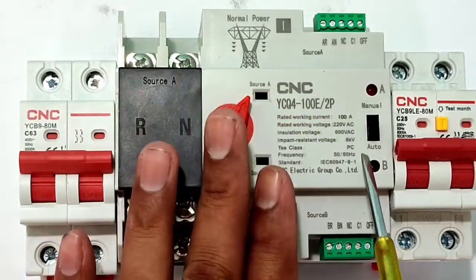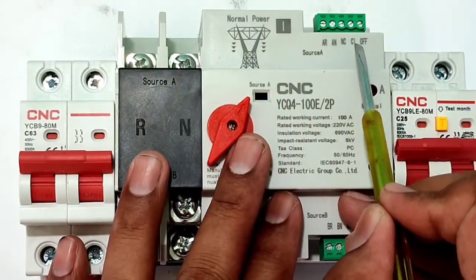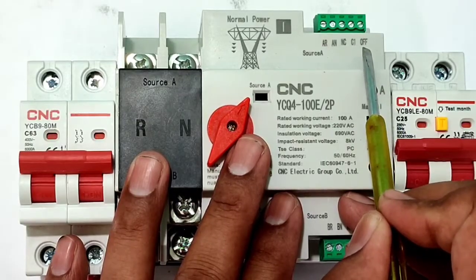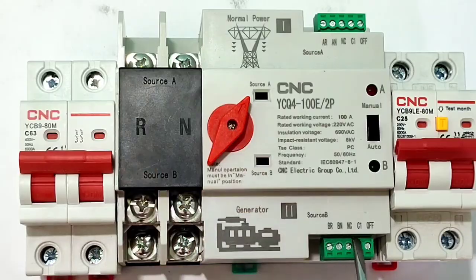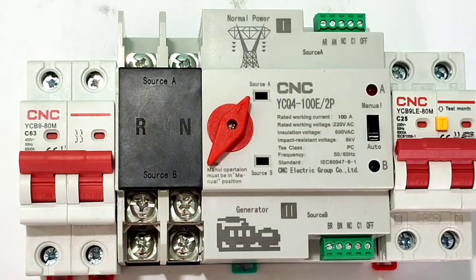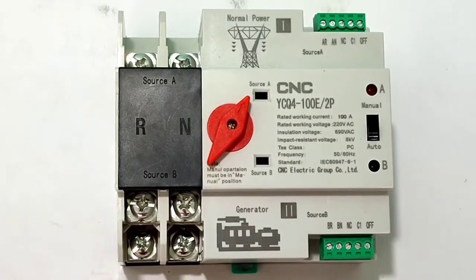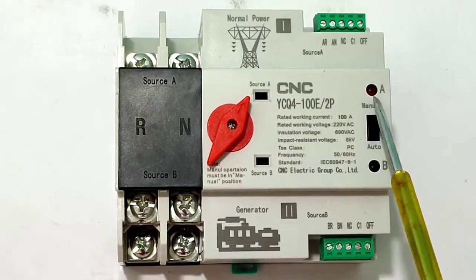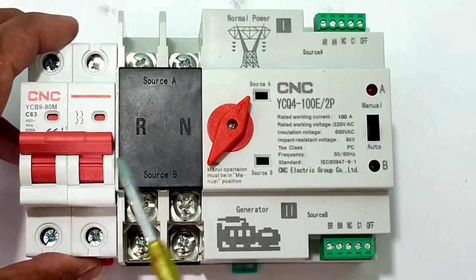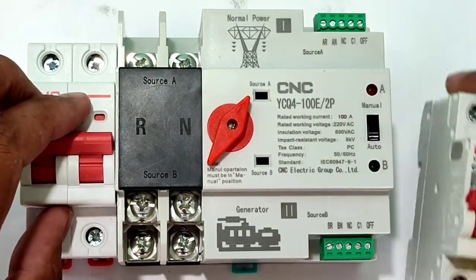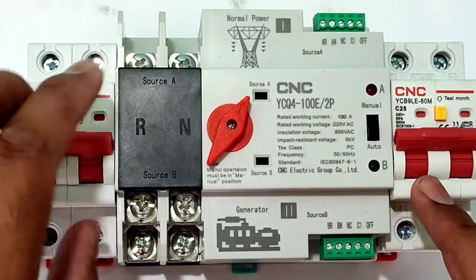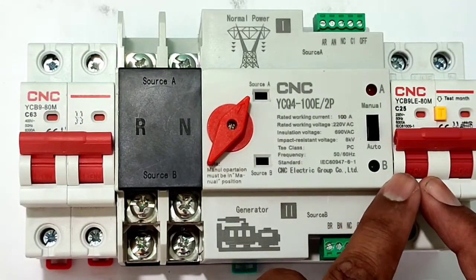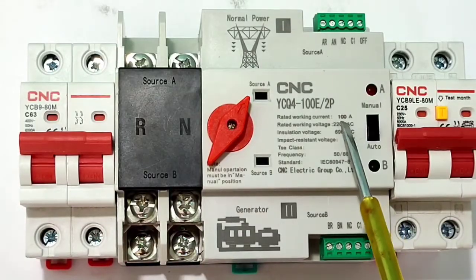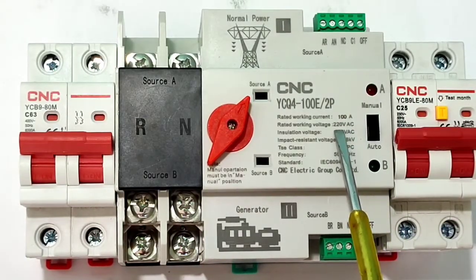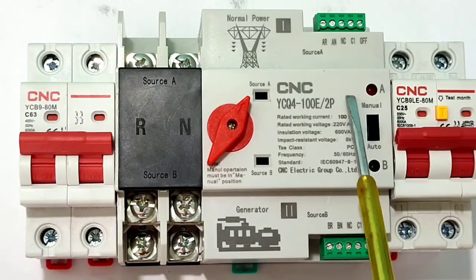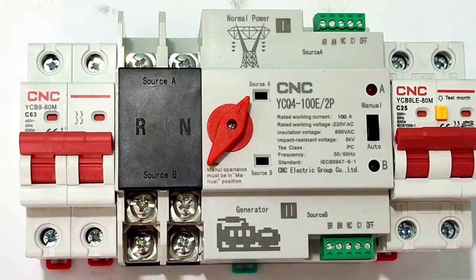And if you want to connect any indicator, trip alarm or buzzer circuit, you can use this relay. You can see here NC, common and off terminals. If you want to connect any indicator, buzzer or alarm, you can use this relay terminal. You can see here we have indicator A. This indicator A is for the main power supply or normal power supply. And also we have indicator B. This indicator B is for the generator power supply or inverter power supply, or whichever is used. So we have two indicators. This automatic transfer switch is used for a 100 ampere load and the operating voltage is 220 volt AC.